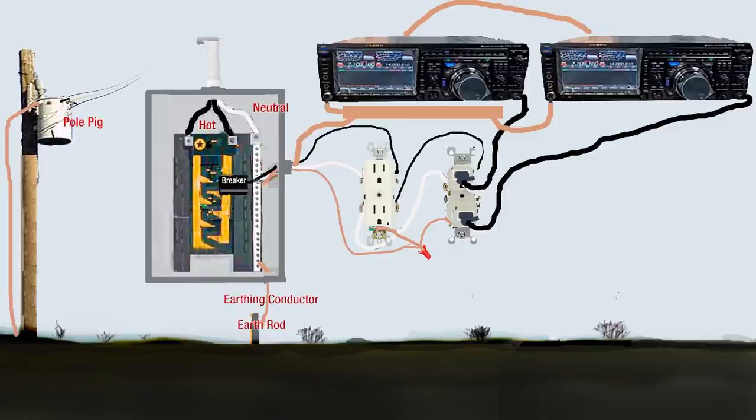A lot of us do that with some kind of pipe, copper tube, flat copper strap behind the equipment, and then there are ground connectors or conductors that go to that plate or tube, and then there's a line that goes from that back to the main panel. Again, it all goes back to one point in the main electrical panel. Having a separate ground connection to one of the transceivers or both would be a violation of the NEC as I read it.